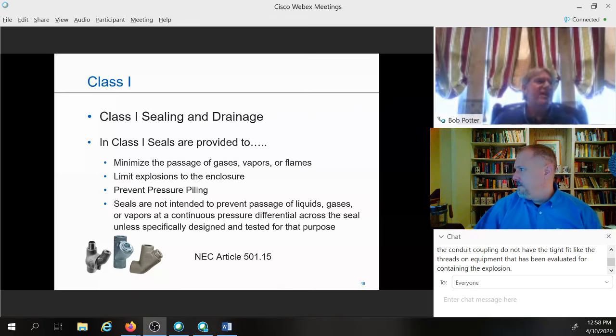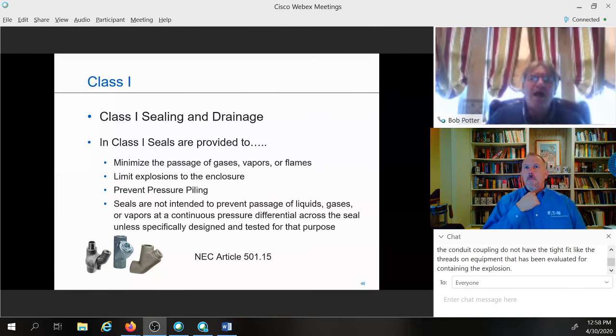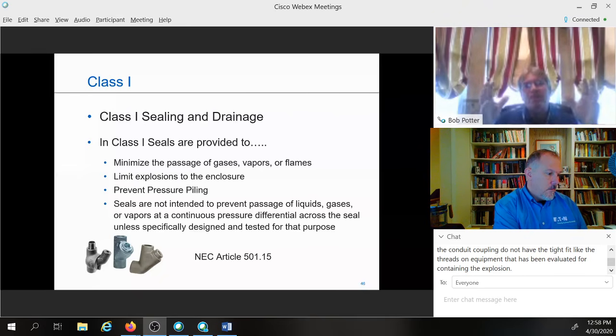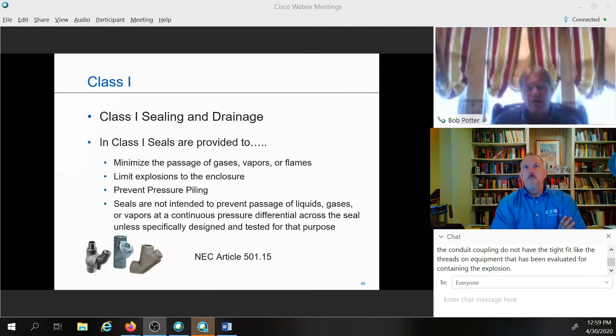Yeah, that was actually not as much of a change, but more word clarifications, because the coupling had been in previous code scenarios. And we'll also be discussing this a little further in the presentation. If I were to have an explosion-proof enclosure and I have a sealing fitting, the code does allow me to put certain explosion-proof fittings in between the sealing fitting and the enclosure. It can help facilitate repair and replacement. It may be because of an obstruction. There could be a number of reasons for that. And so the fittings, though, do need to be certified rated fittings.